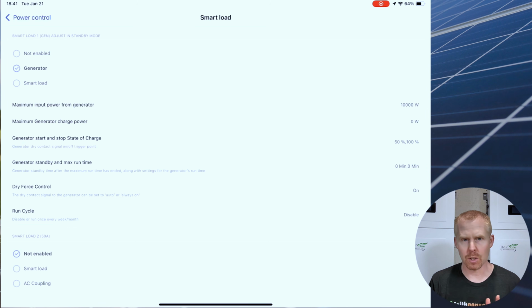And when I say smart load, what I'm saying is it can be configured when it turns on and turns off. So you can set it based on state of charge, you can set it based on voltage, and once it hits certain thresholds, it will turn that breaker on and off to supply loads. If it's in the smart load configuration. If it's in the generator configuration, it'll pull power into the system, and the same with AC coupling.